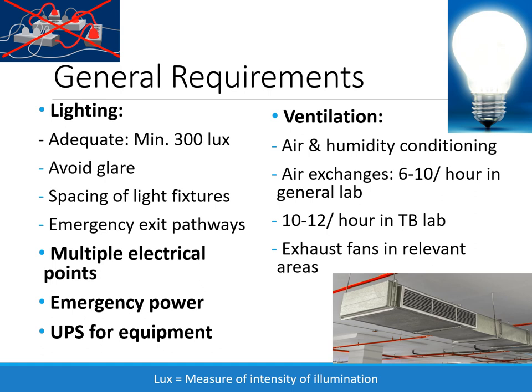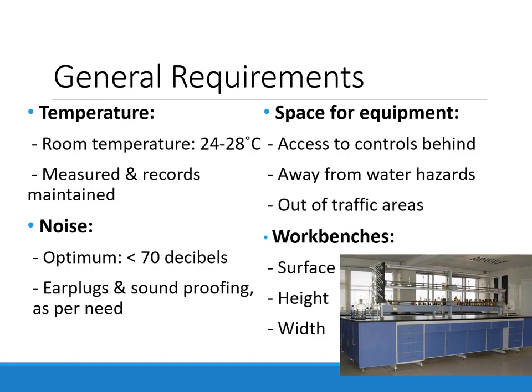Ventilation: the laboratory must have air and humidity conditioning. There must be six to ten air exchanges per hour in a routine diagnostic laboratory and ten to twelve air exchanges per hour in a TB laboratory. Exhaust fans must be fitted in relevant areas.